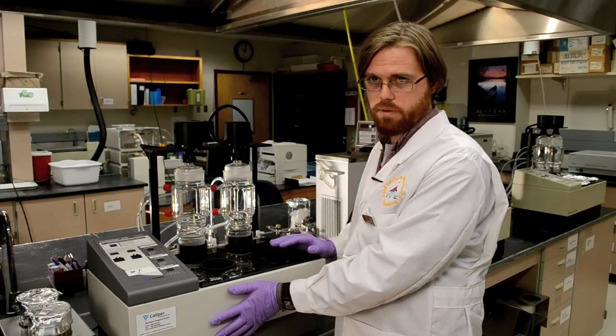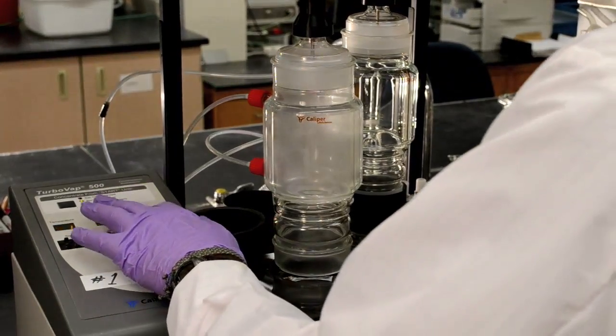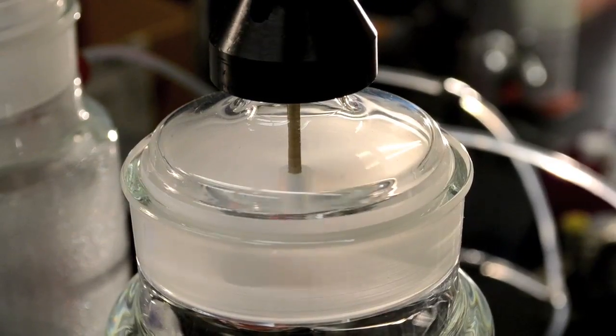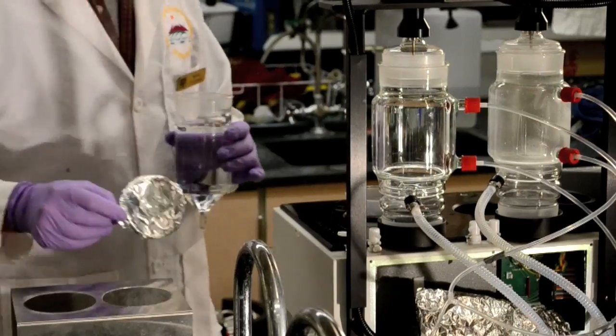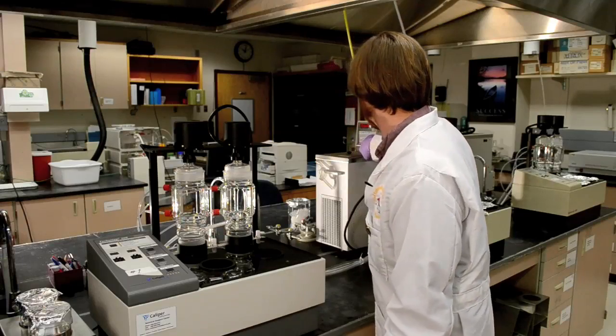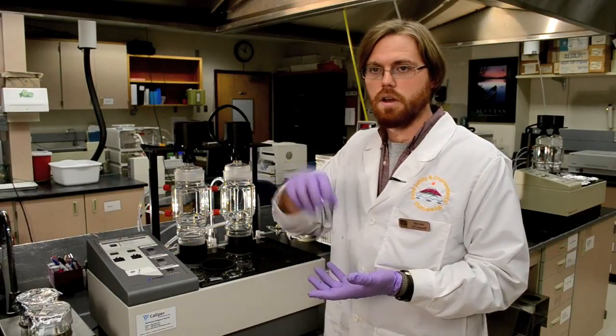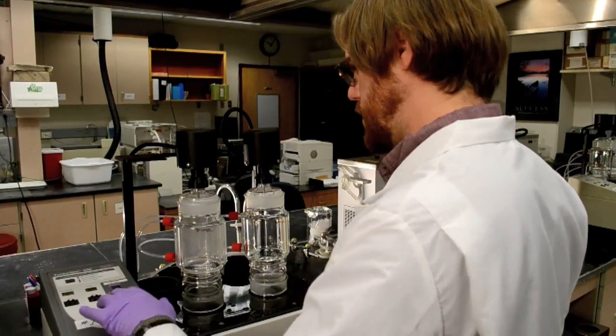What this does is just heats up — we have water in the base here, and we can set our temperature with these gauges right here. That heats up our solvent, and then they evaporate through the top. These are two fans that you can set at multiple speeds. As the process continues, depending on how much solvent you might have, it might take an hour, it might take a few minutes, depending on your starting volume. Typically we're starting with about 400 milliliters. The coolant runs through the double-walled glass right here to keep our solvent from evaporating too quickly, because if you have too much loss, you could actually lose some of your compounds.